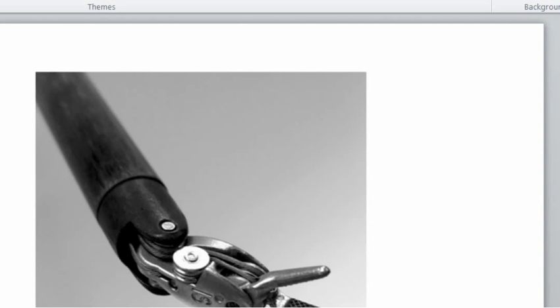All strain gauges were arranged in diametrically opposed pairs to form two symmetric full bridge configurations around the instrument shaft. These configurations offer very sensitive force measurements in two directions perpendicular to the shaft axis, with high signal-to-noise ratio and thermal effect cancellation. Although force acting along the shaft due to tissue pushing and pulling actions cannot be detected.